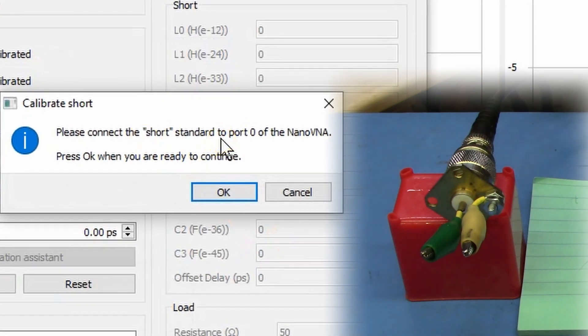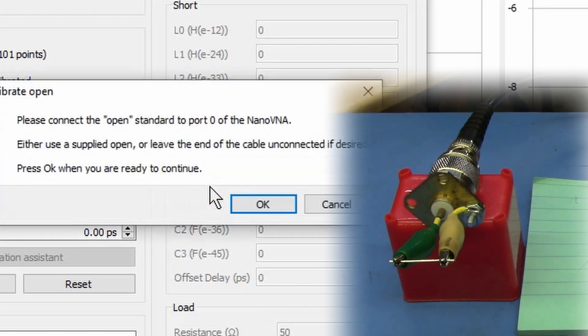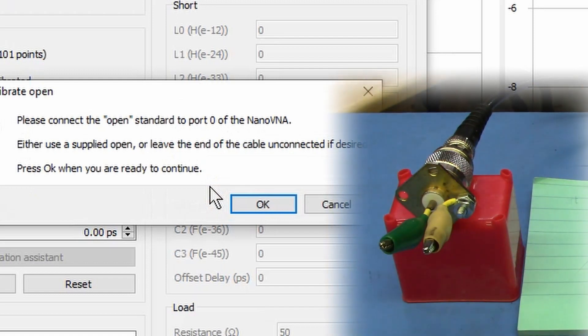Connect the short. So we are going to come here, grab our short. Connect it across our clip leads. There we go. And click on OK. And then we are going to connect up our open. Well, there it is. There is our open.